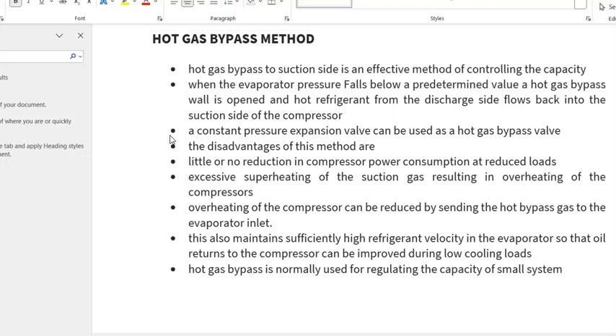In this connection you will see the outlet of the compressor is directly supplied to the inlet of the evaporator, so that all the oil inside the surface of the tube of the evaporator can be removed and come back to the suction side and crankcase of the compressor. It's very important. But this method is not effective because there is no reduction in compressor power consumption, and superheating of the suction gas results in compressor overheating.